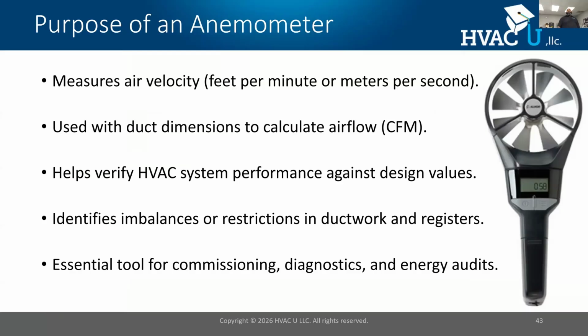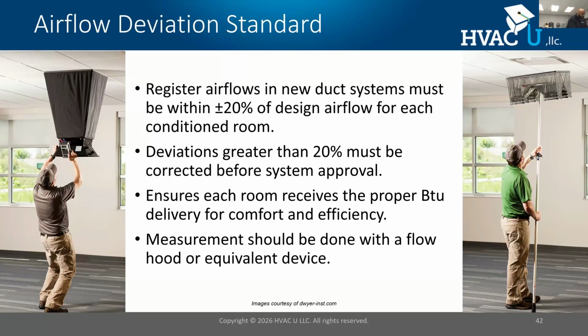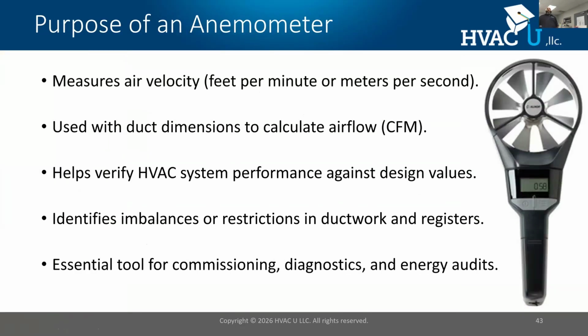Oftentimes, this device is going to be hard to use. This is a flow hood here. Sometimes this may be impractical to use. We may have to switch to this. This is a vane anemometer. What its purpose is, it measures air velocity in feet per minute or meters per second. And what it's used for, I can measure the airflow coming out of a register or grill. Now, there's a little math that I have to do. This only measures feet per minute, and I have to do the equation to figure out what surface area I have, and if I have the AK ratings on registers or grills.